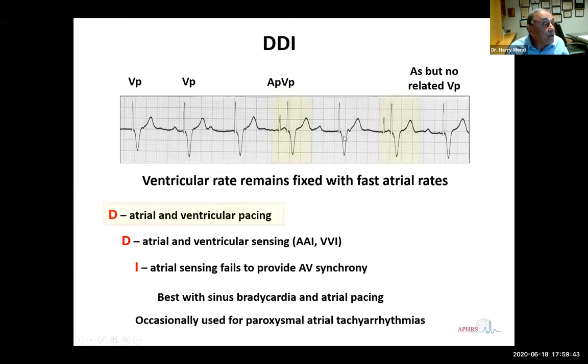We can see in this example there is atrial pacing and ventricular pacing, which accounts for the first D. Although we actually cannot see it, there is atrial and ventricular sensing. The P waves that you see are actually sensed, but the atrial sensing fails to provide AV synchrony, and the ventricular paced rate therefore remains at a fixed rate unless there is rate adaptive pacing. This type of rhythm disturbance could be looked at as being AAI and VVI, and when we put them together, when we have an atrial tachyarrhythmia, the ventricular pacemaker does not follow at a fast rate.